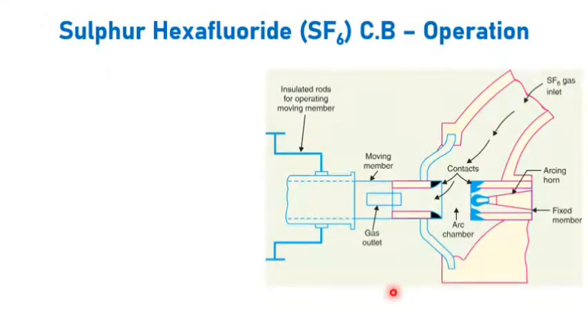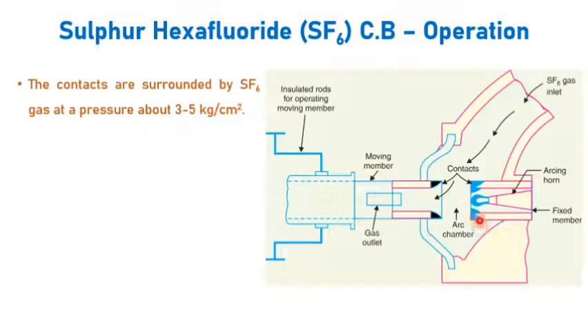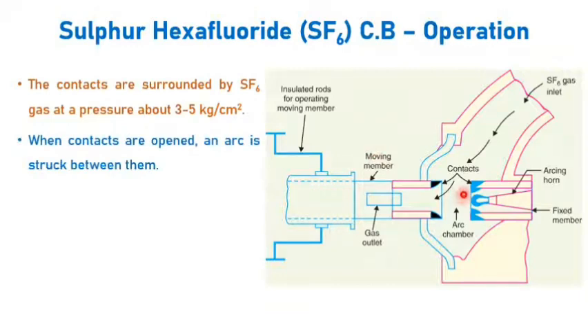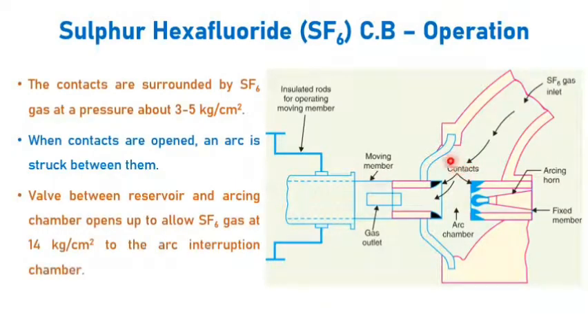Let us see the operation of the SF6 circuit breaker. During no fault condition, both the contacts will be in closed condition, and as I said before, the contacts are surrounded by SF6 gas at a pressure of 3 to 5 kg per centimeter square. When contacts are opened, an arc is struck between the fixed and moving contacts. So the valve of the arcing chamber, as this is called, opens and SF6 gas at 14 kg per centimeter square enters into the arcing chamber.